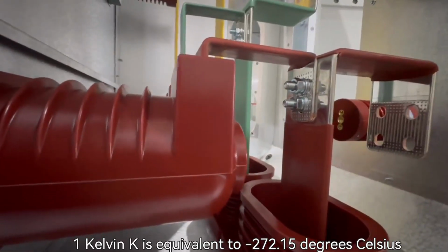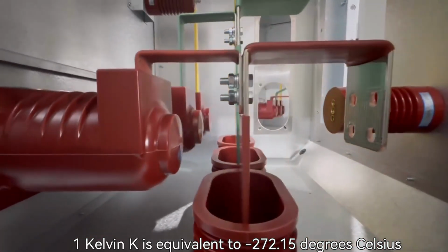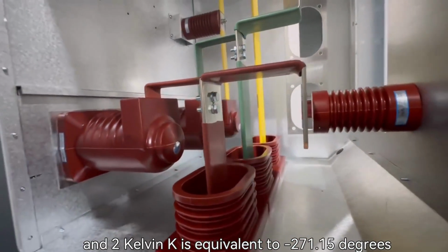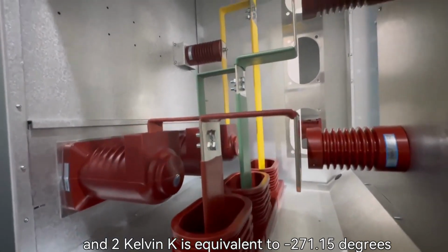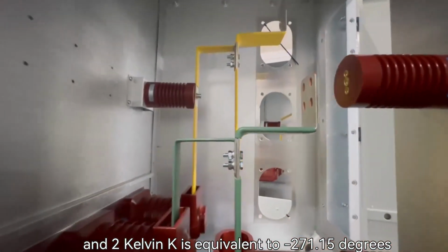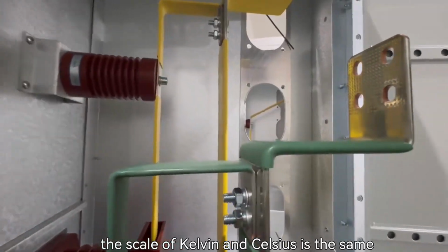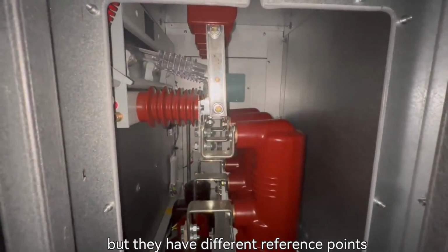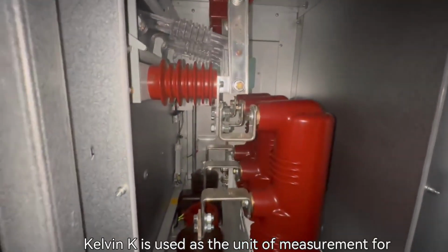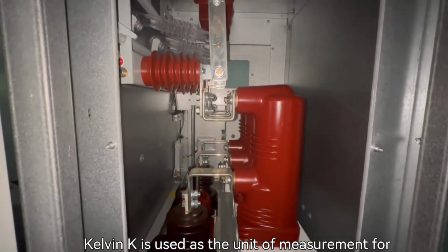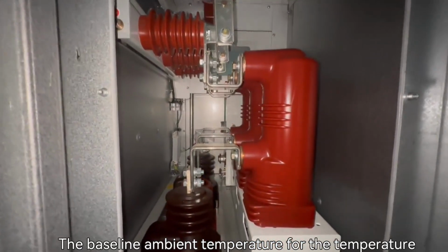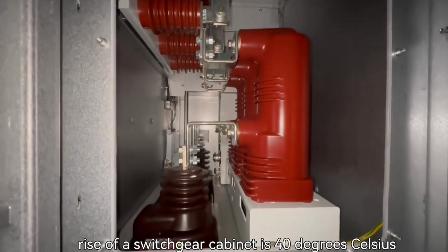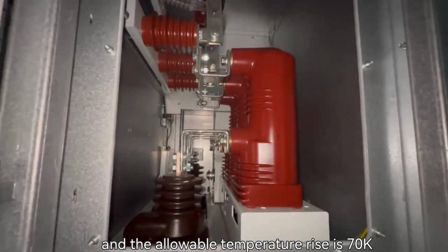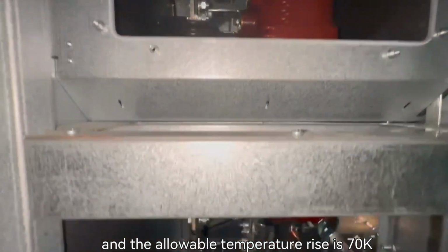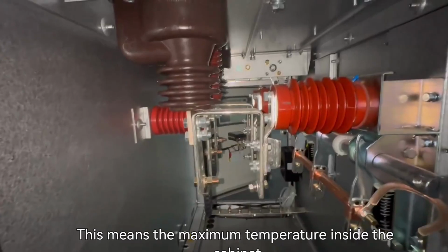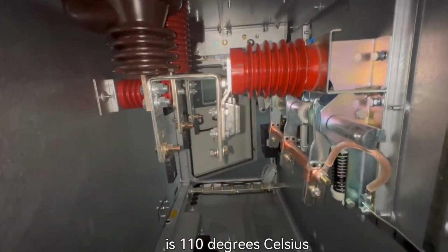Specifically, 1 Kelvin K is equivalent to minus 272.15 degrees Celsius, and 2 Kelvin K is equivalent to minus 271.15 degrees Celsius. In practice, the scale of Kelvin and Celsius is the same, but they have different reference points. Therefore, Kelvin K is used as the unit of measurement for relative temperature rise. The baseline ambient temperature for the temperature rise of a switchgear cabinet is 40 degrees Celsius, and the allowable temperature rise is 70 K. This means the maximum temperature inside the cabinet is 110 degrees Celsius.